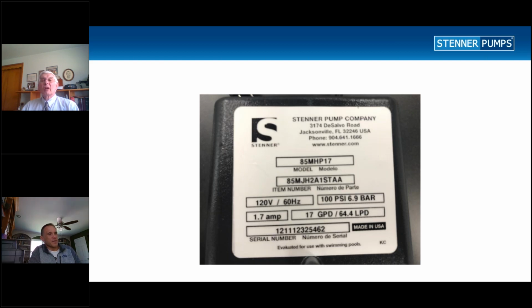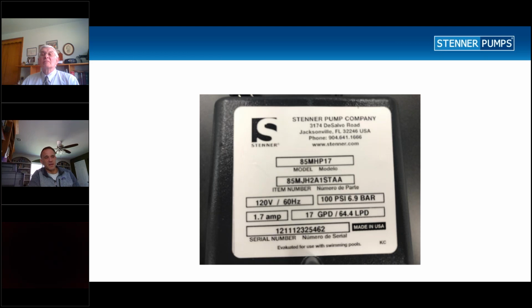When I look at the serial number, the first 2 numbers represent the month. The second 2 numbers represent the date that it was manufactured. And the 5th and 6th numbers represent the year that it was made. So if you're trying to figure out if a pump is under warranty, we base warranty off of 2 different scenarios. One, either by the final bill of sale to your customer when they purchase it, or we will go by the serial number on the pump itself, or the date code. In this case, because this pump has a 1-year warranty, the pump itself would technically be out of warranty.